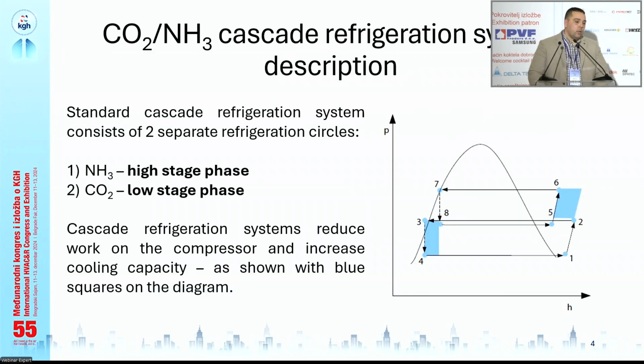I will just go shortly through the basic description of the CO2 ammonia cascade refrigeration system. As we already said, we have on the pH diagram two circuits. The lower one is the CO2 circuit, and the top one is the ammonia circuit. As you can see, of those two blue areas, the lower left one represents the increase in the total refrigeration capacity of the system, and on the right corner, we have a blue area that represents the reduction of the work on the compressors.